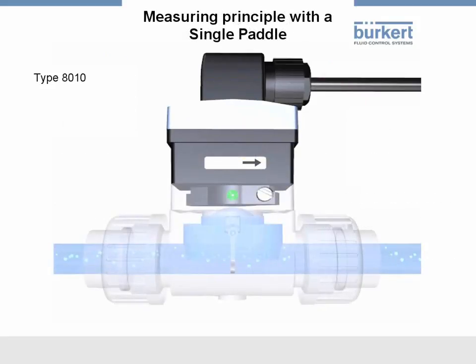The next process uses a paddle wheel in the form of a single paddle, which includes a permanent magnet. The paddle is mounted so that it can move in the direction of flow. If no medium is flowing, the paddle is in vertical position. If a certain flow rate is exceeded, it tilts in the direction of flow and switches a reed contact. In this case, there's no measurement, only the presence of a flow is detected and signaled.